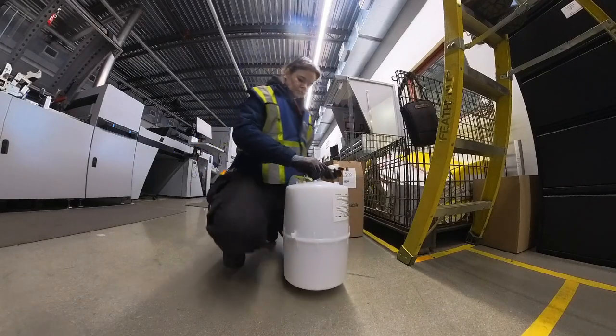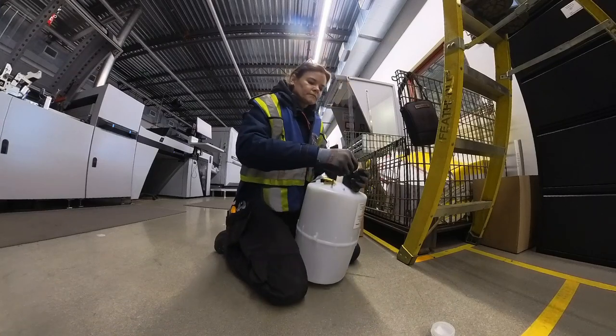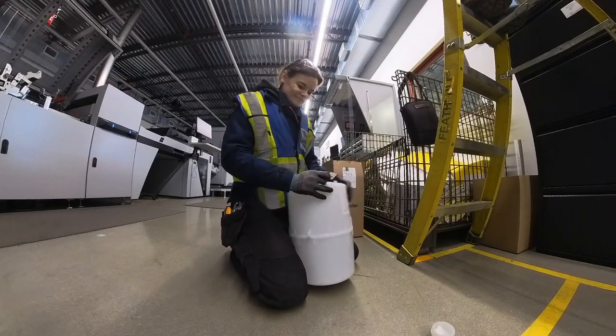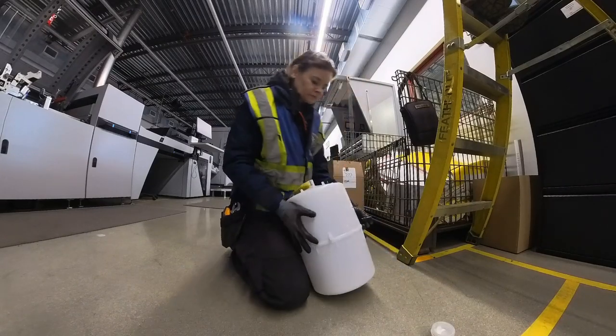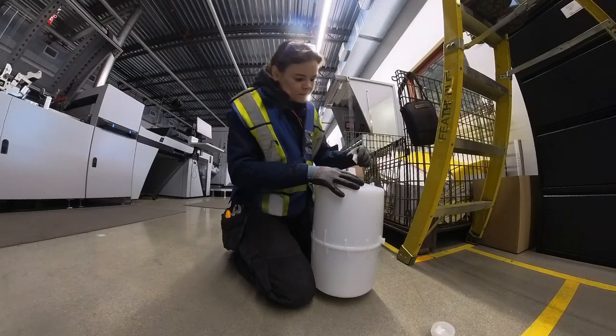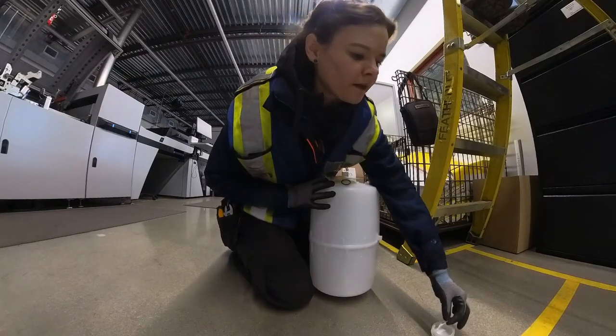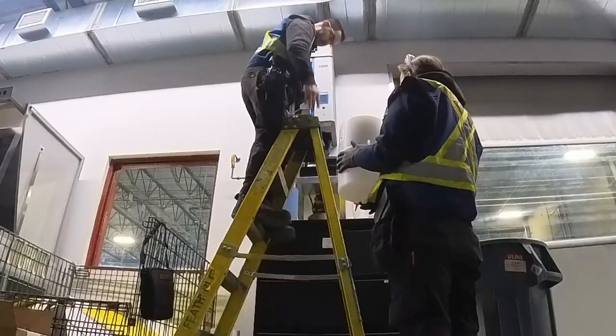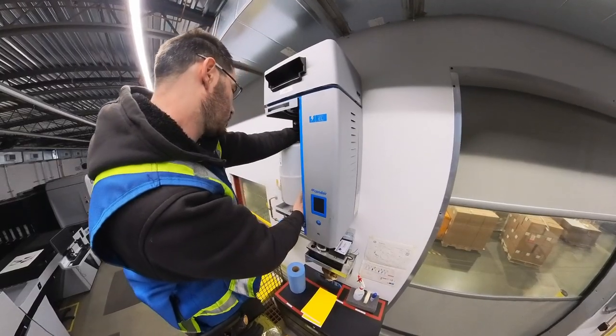With the new pot, it's a trick of the trade to add a little package of iodized table salt, and this is supposed to help the conductivity of the water inside the pot. These humidifiers don't actually have heaters inside them — they've got two electrodes that are immersed in water, and those electrodes are connected to live and neutral. The water they're submerged in actually conducts the electricity they need, and sometimes fresh water just doesn't have enough conductivity, so we add table salt. There was a bit of a discussion on my Instagram about this because apparently this trick of the trade has been debunked — you don't need to add table salt anymore. But anyway.